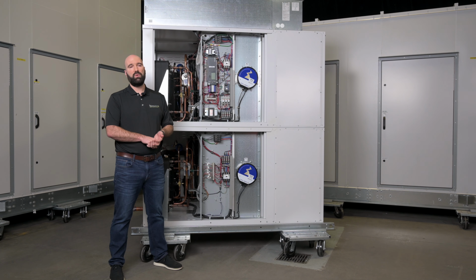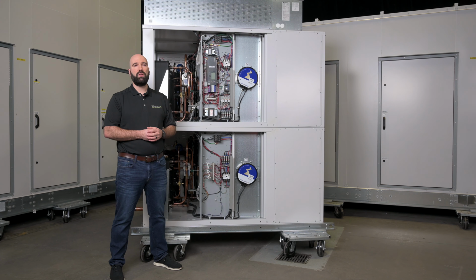And that electric heater is really only there as emergency heat. If you were to have a catastrophic compressor failure, but really more likely you've got a power outage or something like that, and your facility is cold and dark and you need to bring it back up to temperature quickly. Those electric heaters, because of our capacity for 100% reheat, are not used in everyday operation. We've got many units out there that are electric heater equipped that just don't have them, but needing it and not having it is a problem, and so they're standard on all of our equipment.